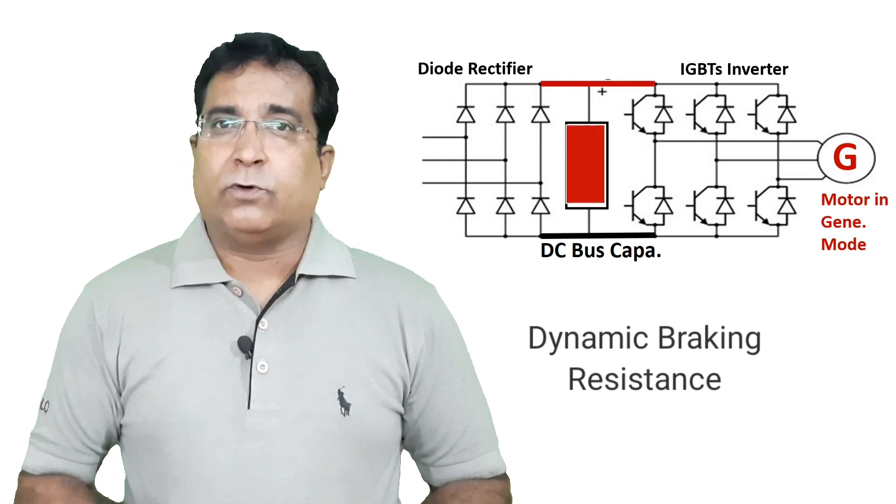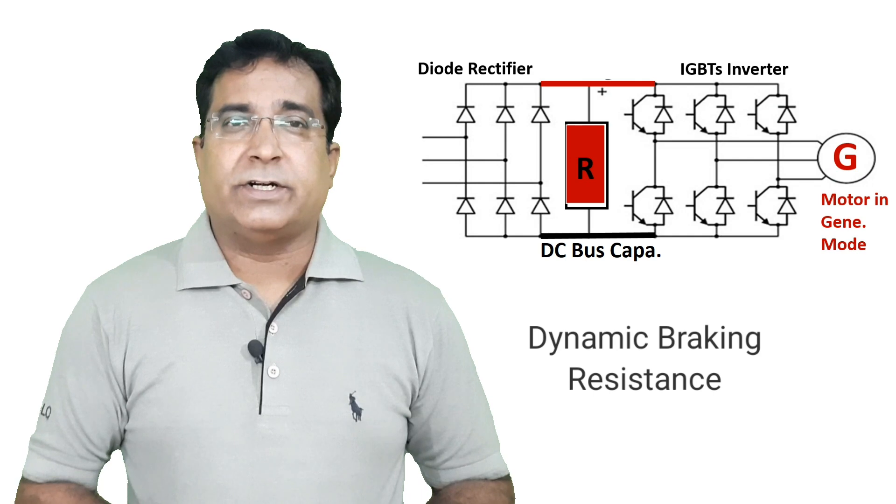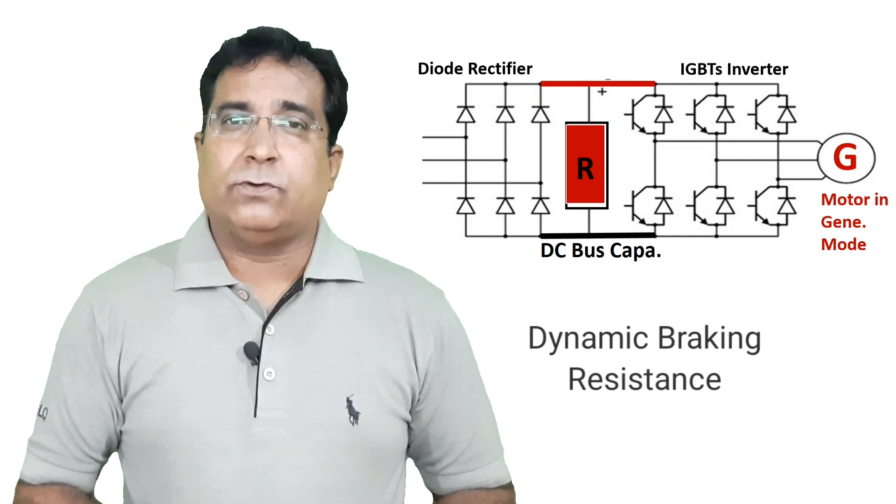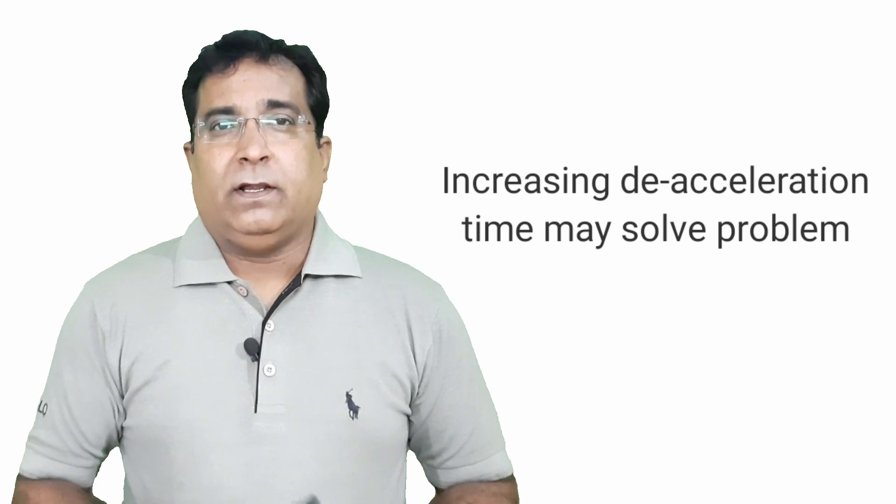Basically this resistance puts a load on motor and burns all its regenerated energy causing motor to stop. That is why this process is also called dynamic braking. This problem can also be solved by increase in the deceleration time in speed reference. If it does not solve the issue of DC bus voltage then adding a dynamic resistance becomes the solution.